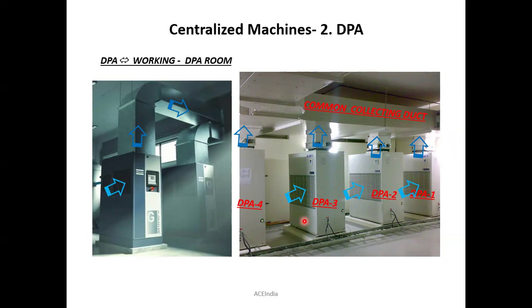So what is the relevance of this thing? You know, inside these machines, you can see this fan, especially a closed type fan. So it will literally create a lot of vibrations, isn't it? So in order to damp the vibrations, that's why we provide this kind of floor raising along with the rubber pad connection. In other words, if you place these machines directly on the floor, the noises or the vibrations can be resonated on the floor below.